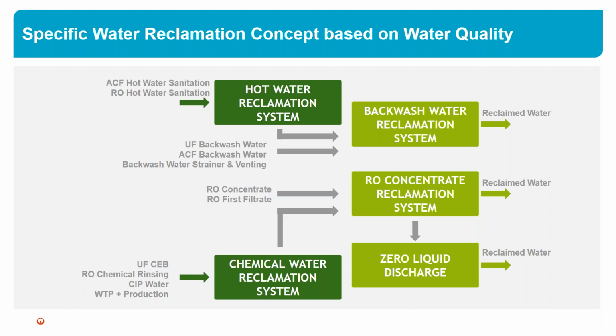I'd like to briefly give an example of how backwash water reclamation could look. The main process step here is ultrafiltration, and for RO concentrate, it's a reuse RO. Of course, we can't go very high with the recovery because it's already a concentrated stream, so we're limited to around 60 to 70% recovery, otherwise we'd have scaling.